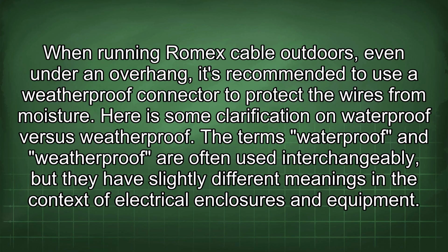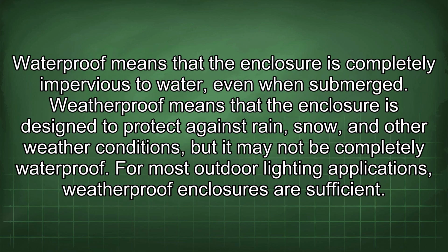Here is some clarification on waterproof versus weatherproof. The terms waterproof and weatherproof are often used interchangeably, but they have slightly different meanings in the context of electrical enclosures and equipment. Waterproof means that the enclosure is completely impervious to water, even when submerged. Weatherproof means that the enclosure is designed to protect against rain, snow, and other weather conditions, but it may not be completely waterproof. For most outdoor lighting applications, weatherproof enclosures are sufficient.